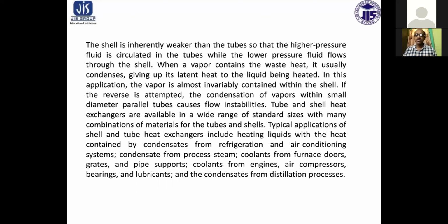When a vapor contains the waste heat, it usually condenses, giving up its latent heat to the liquid being heated. In these applications, the vapor is almost invariably contained within the shell. So the vapor, which contains waste heat, usually condenses in the shell, and this type of heat exchanger is also termed a condenser, where the vapor is being condensed.